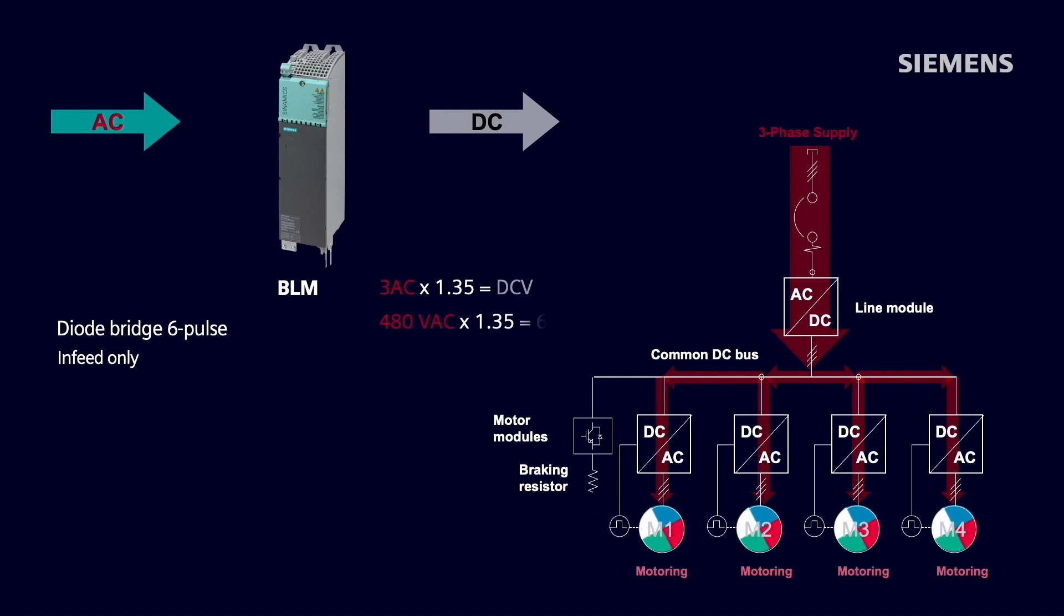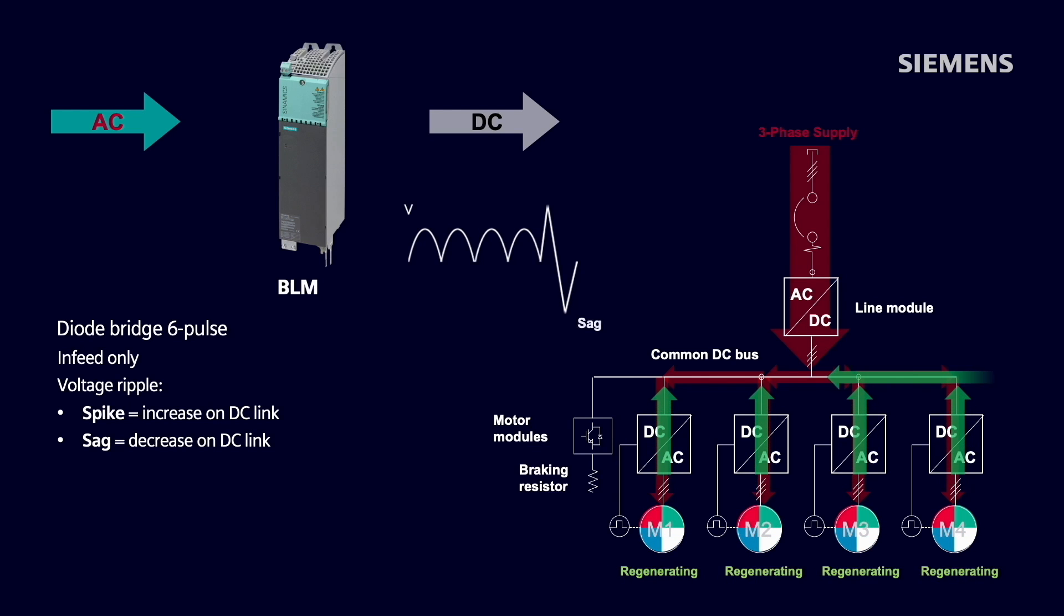With a 480-volt three-phase infeed, we'd be powering a 650-volt DC bus, which would have a certain amount of voltage ripple on it from the diode bridge. If we have load hits on the motor or voltage sags on the incoming power, we would see a decrease on the DC link. And vice versa, if we were regenerating power back to the DC link or we had voltage spikes, we would see an increase on that DC link as well.